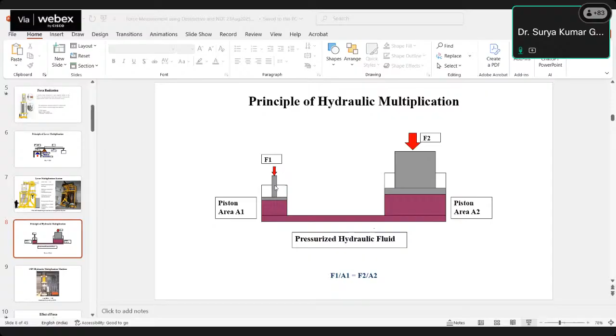We have one such machine at NPL using hydraulic multiplication, with an area ratio of 100 times. With the lever method we can increase force up to 10 times, but with this hydraulic method we can increase it up to 100 times. The dead weight here is only 10 kN, and by multiplying 100 times, we get 1000 kN force value on the other side.